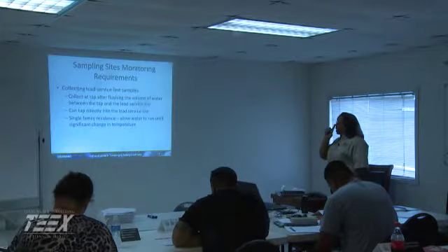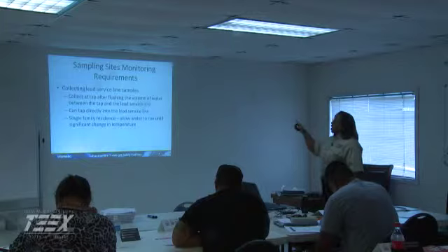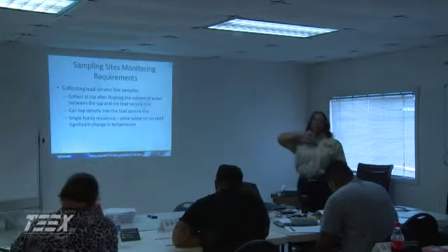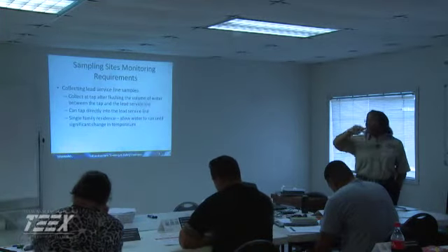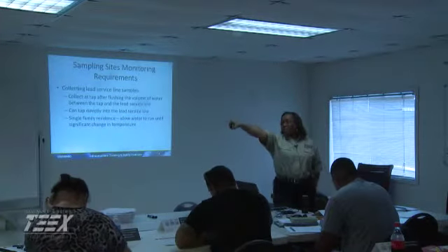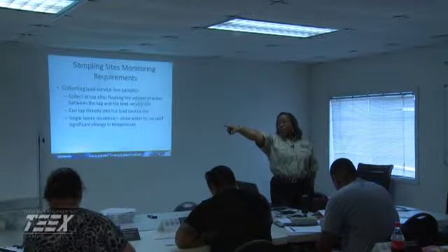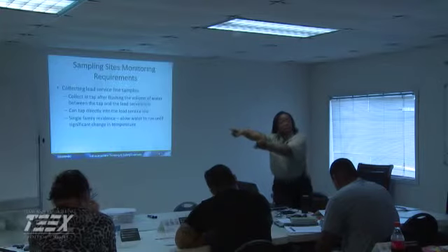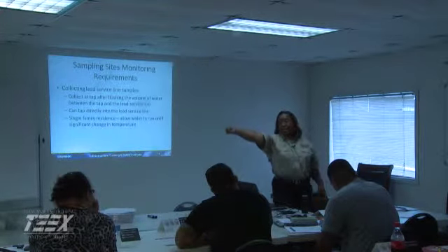Okay, collect a tap after flushing the volume of water between the tap and lead service line when you are collecting lead service line samples. This is different from the tap, though. In other words, if I want that water from that lead service line, and that lead service line is actually out there on the other side of the road, I need to make sure I'm flushing enough water where I'm pulling the water that's stagnant in that line out there.